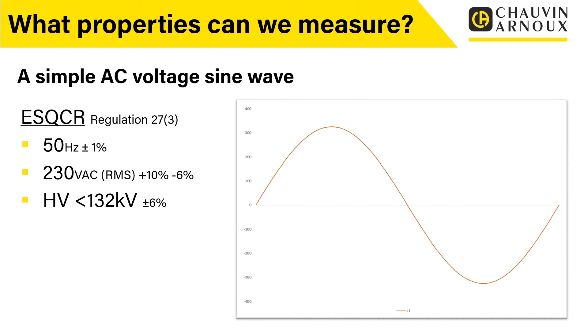Now, in the UK, we've got something called the ESQCR, the Electricity Safety, Quality and Continuity Regulations. And these lay out, in very basic terms, the standard for the electricity supply. So it should be 50 hertz plus or minus 1%. It should be 230 volts AC RMS plus 10% minus 6%. And for those of you who take a high voltage supply directly from the grid, from the suppliers, if it's less than 132 kilovolts, it should be plus or minus 6%. And if it's over 132 kilovolts, it's allowed to be plus or minus 10%. And that's what's laid out in the ESQCR.